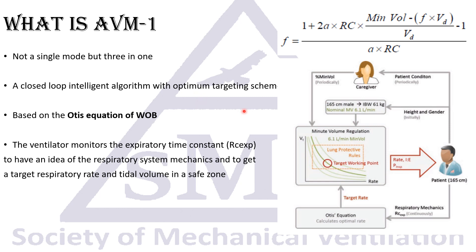I encourage you to read the taxonomy by Chatburn. AVM1 is based on the Otis equation, which was later modified by Mead — the Otis-Mead equation of the work of breathing. That equation defines a window: the range of respiratory rates and tidal volumes associated with the least work of breathing. We either have a very large tidal volume with a very low respiratory rate, or very shallow breaths with a low tidal volume and very high respiratory rate. The ventilator monitors the expiratory time constant to adjust its target respiratory rate and tidal volume to be in that safe zone.